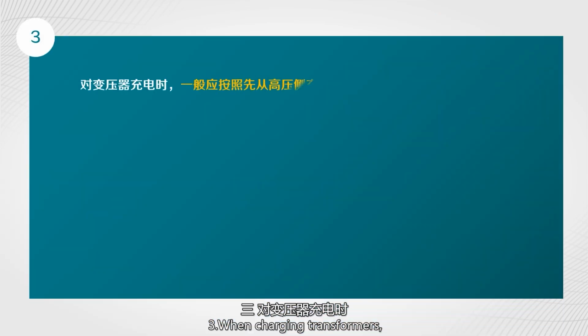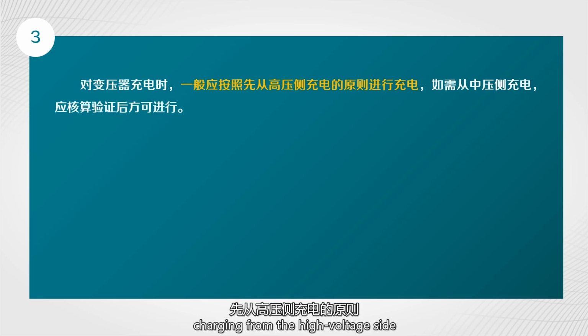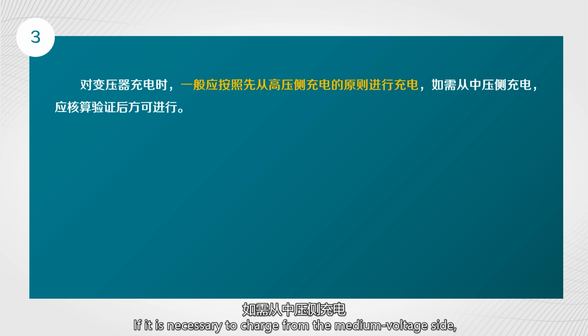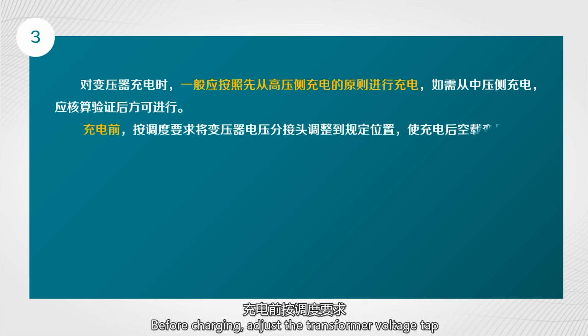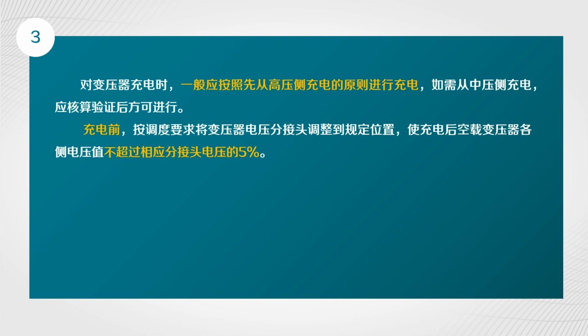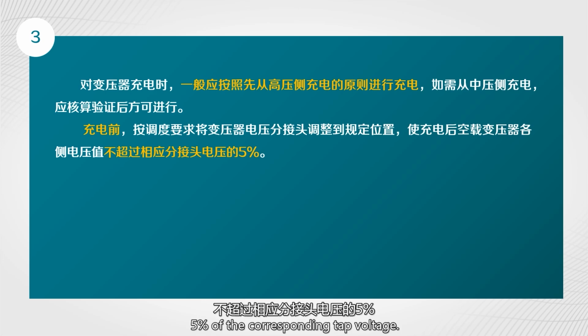Third, when charging transformers, the principle of charging from the high voltage side should generally be followed. If it is necessary to charge from the medium voltage side, it should be verified before proceeding. Before charging, adjust the transformer voltage tap to the specified position according to the scheduling requirements, so that the voltage value on each side of the no-load transformer does not exceed 5% of the corresponding tap voltage.